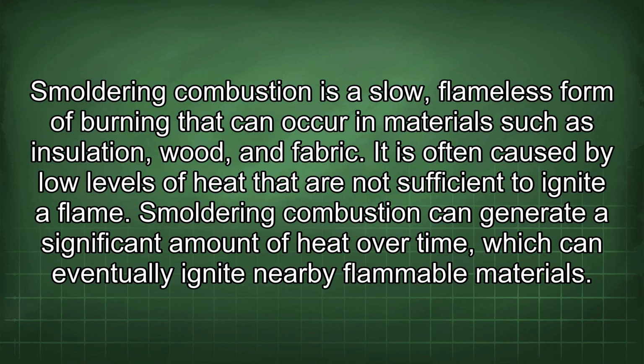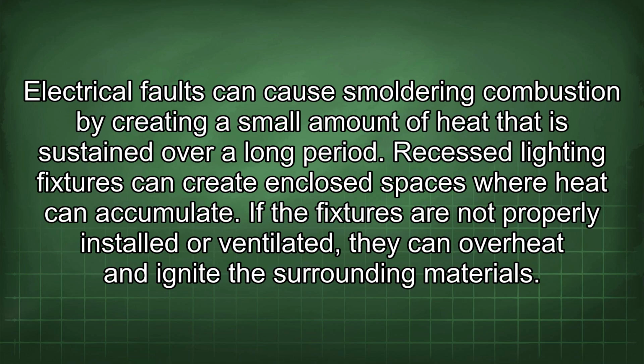Smoldering combustion is a slow, flameless form of burning that can occur in materials such as insulation, wood, and fabric. It is often caused by low levels of heat that are not sufficient to ignite a flame. Smoldering combustion can generate a significant amount of heat over time, which can eventually ignite nearby flammable materials. Electrical faults can cause smoldering combustion by creating a small amount of heat that is sustained over a long period.